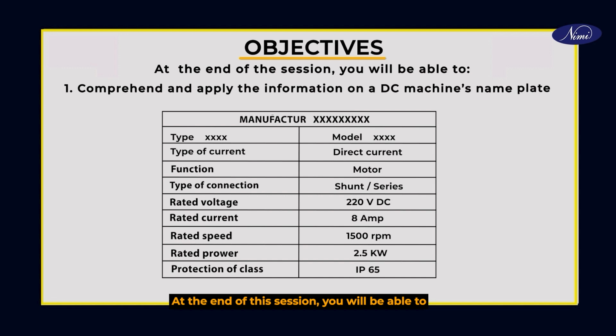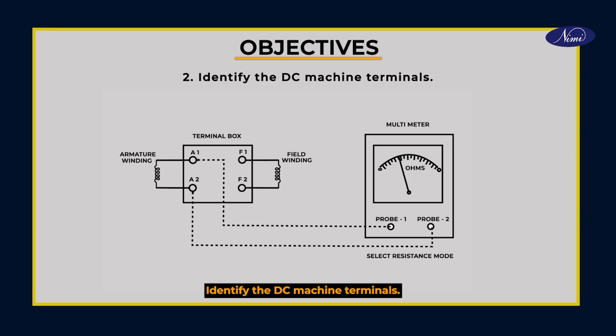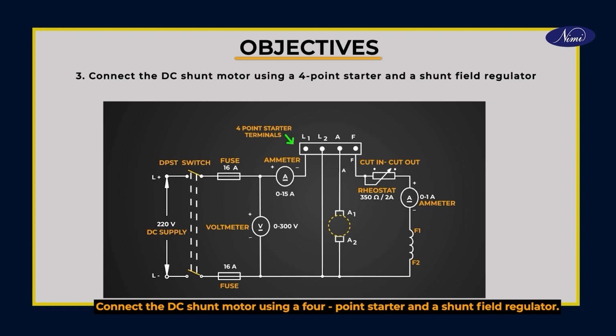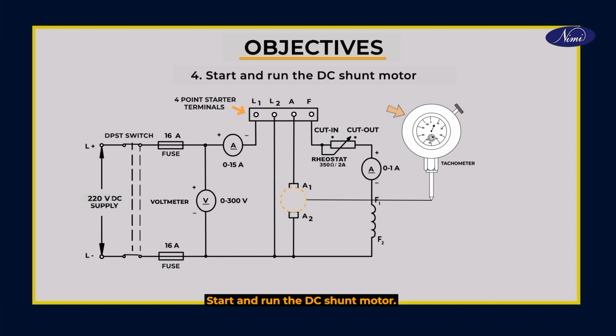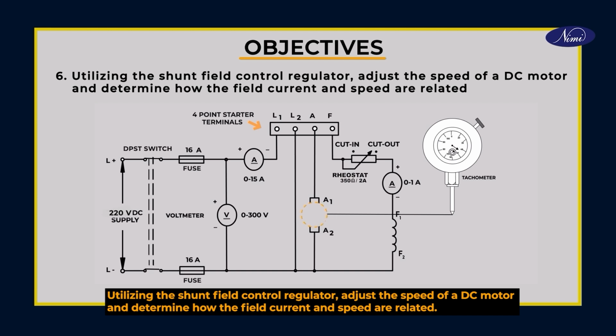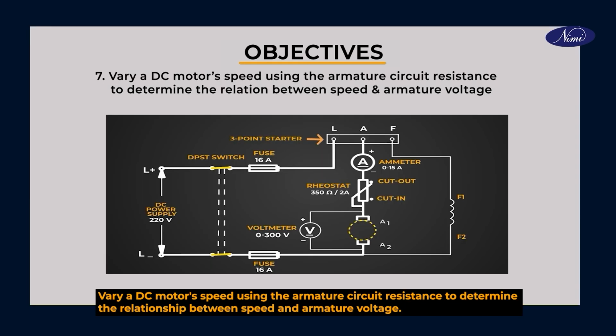At the end of this session, you will be able to comprehend and apply the information on a DC machine's nameplate, identify the DC machine terminals, connect the DC shunt motor using a 4-point starter and a shunt field regulator, start and run the DC shunt motor, measure the speed of the motor, utilizing the shunt field control regulator, adjust the speed of a DC motor and determine how the field current and speed are related. Vary a DC motor's speed using the armature circuit resistance to determine the relationship between speed and armature voltage.